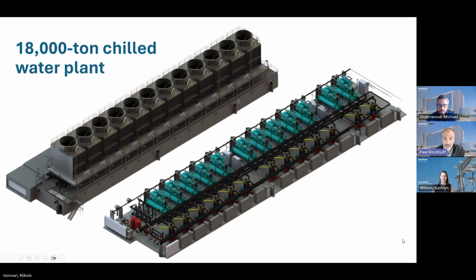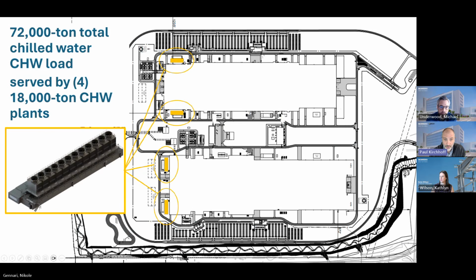If you go to the next slide, you'll see the actual solution we came up with. During the design assist process, we sat down with everybody, and the implications of a single 70,000 ton plant became obvious, so we said, why don't we do four identical 18,000 ton plants instead? That worked out really well for a couple of main reasons.